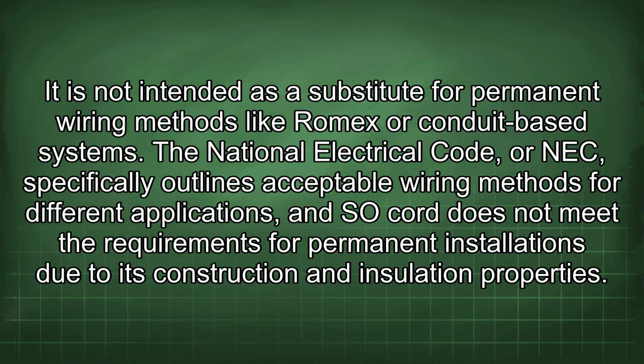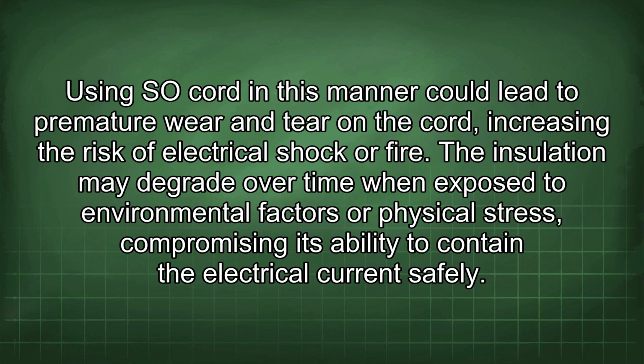The National Electrical Code, or NEC, specifically outlines acceptable wiring methods for different applications, and SO cord does not meet the requirements for permanent installations due to its construction and insulation properties. Using SO cord in this manner could lead to premature wear and tear on the cord, increasing the risk of electrical shock or fire. The insulation may degrade over time when exposed to environmental factors or physical stress, compromising its ability to contain the electrical current safely.